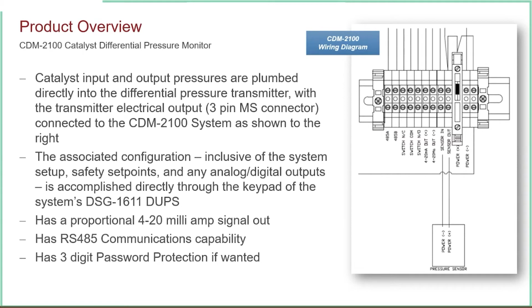Also, once you calibrate this product, it may not be a bad idea, with your communications if you're using it, and the 4 to 20, to set a 3-digit password so nobody goes in and changes your set points, messes with your communications or your 4 to 20 calibration. Like I said, you can protect just communications, just set points, or you can protect everything with a 3-digit code if you wanted with the 1611.